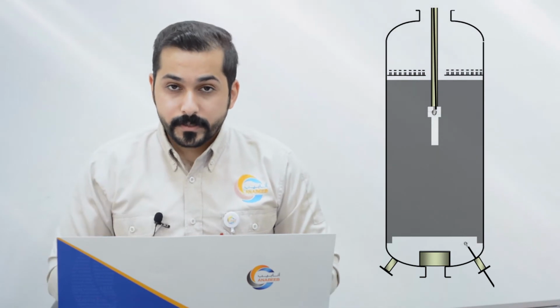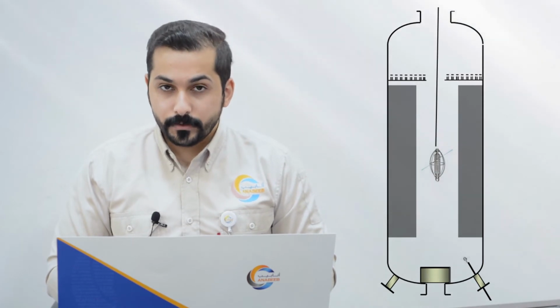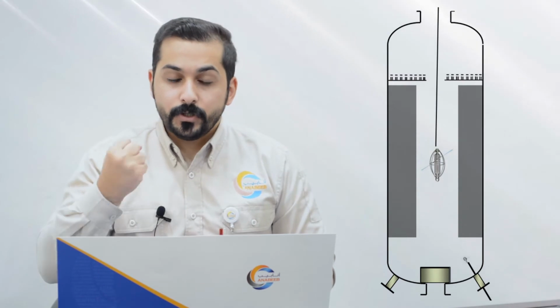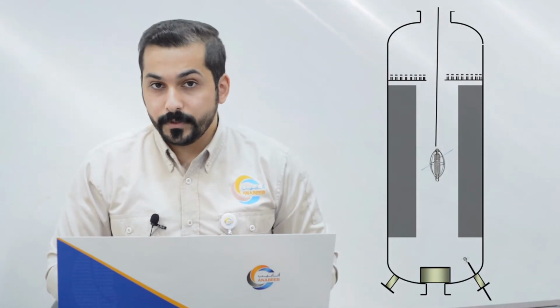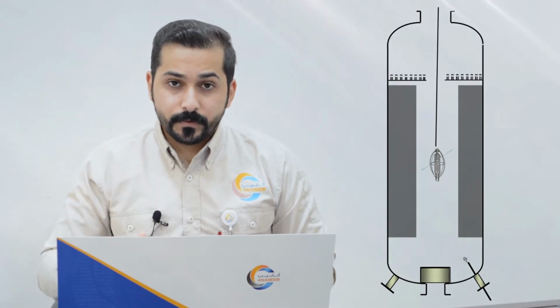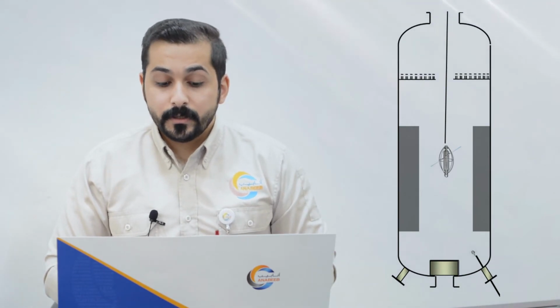The second step, which is unloading, is unloading by the primary drill head and the cleaning nozzle. When it's drilled, it has high pressure water to break the fused catalyst and flush it through the way out from the dump nozzle. The third step, which is the final clean by the cleaning nozzle, can clean and flush the reactor.